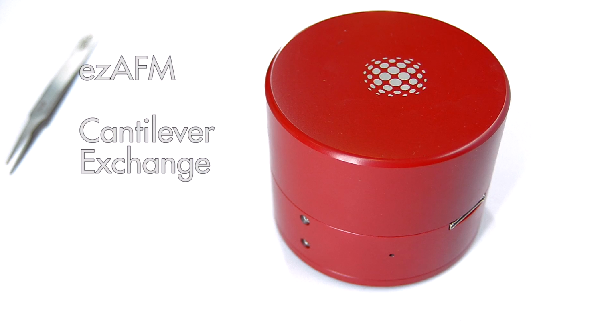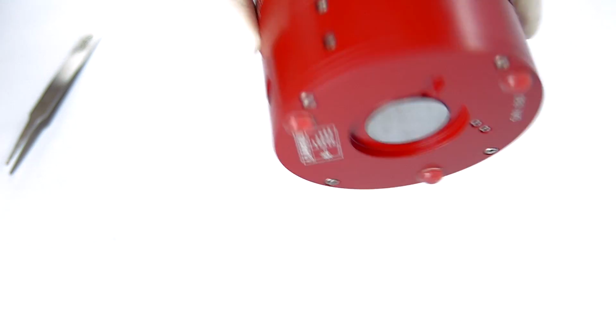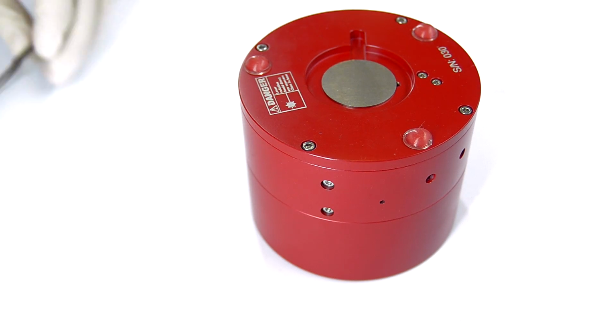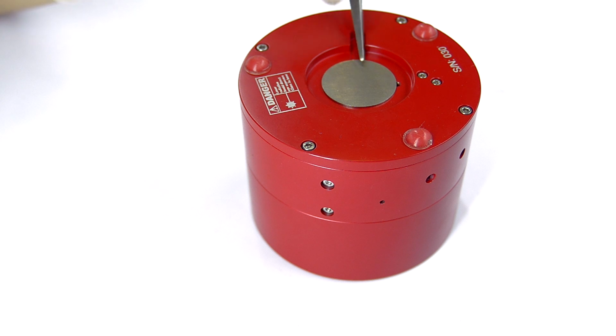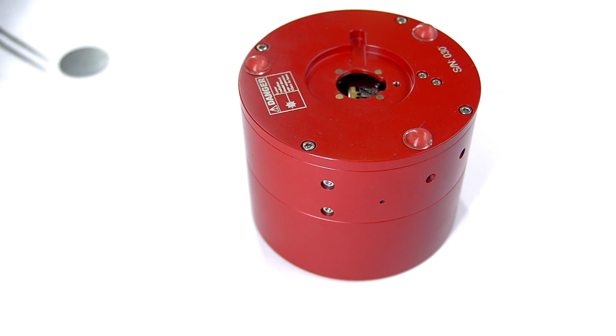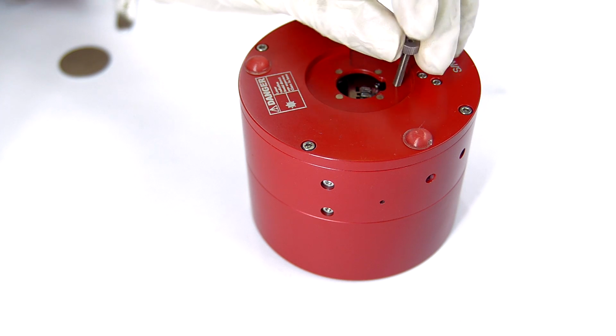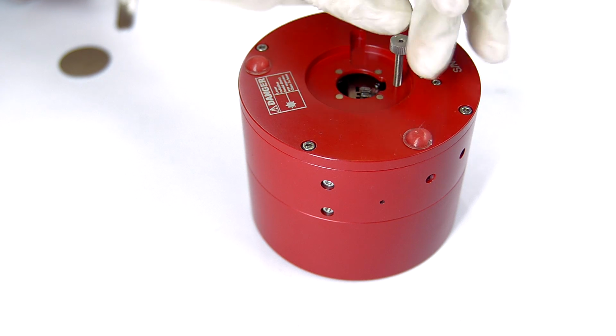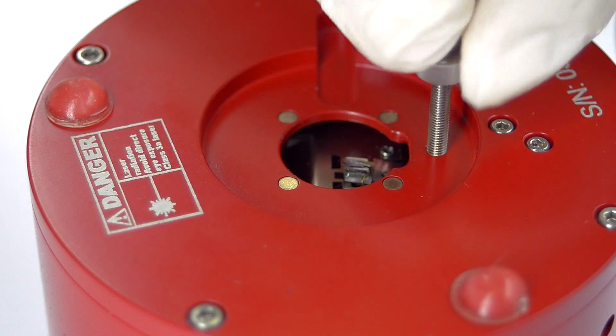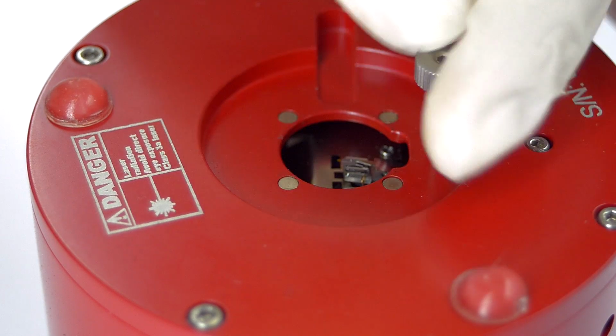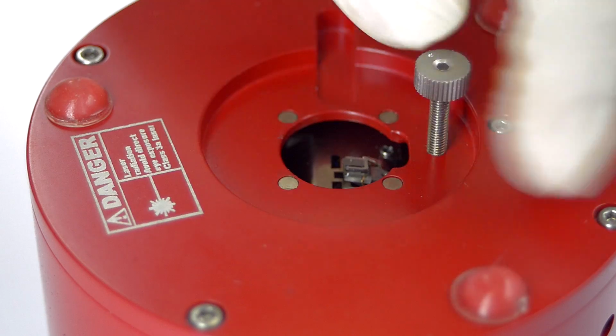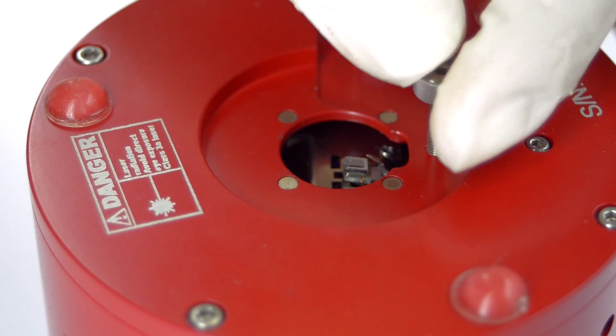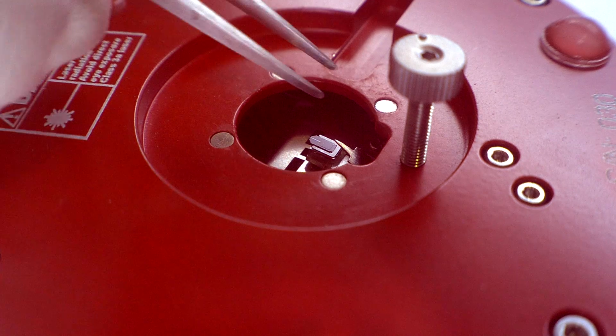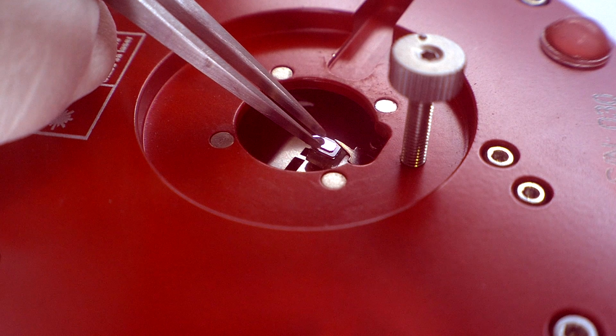With the ezAFM, Cantilever Exchange is a remarkably simple process. Remove the sample holder from the bottom. Thread the thumb screw until the spring-loaded fulcrum releases the cantilever. Using tweezers, remove the existing cantilever.